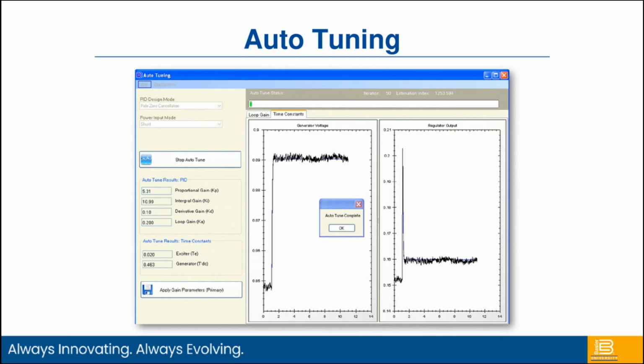Here's a screenshot of our auto tuning function. Basically what we would do is connect to the unit and start it, then during auto tune I can hit start. You can see it's doing a few step responses, a little bump, looking at generator outputs, and then a large step response, and then it runs through some cycling to make sure. Once it's complete, we'll get a button that says auto tuning is complete, and then I can apply those gains.